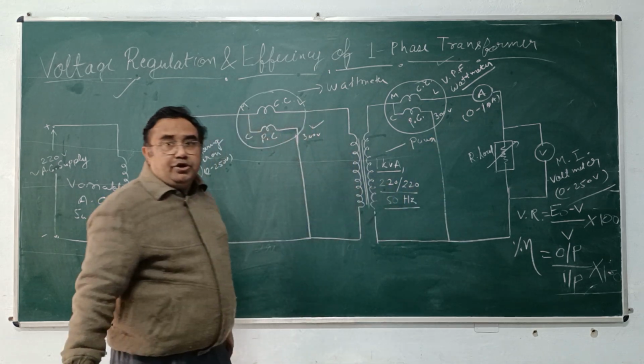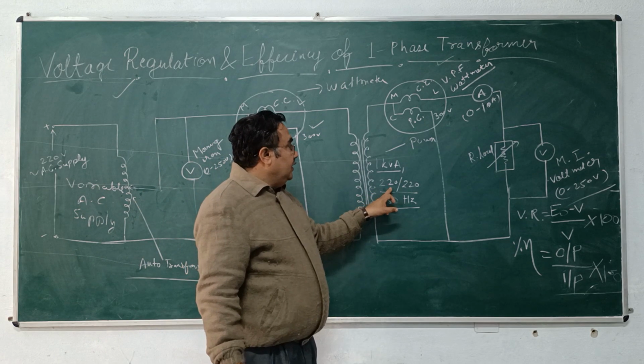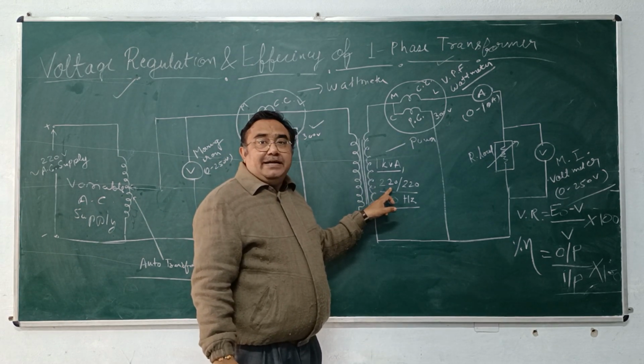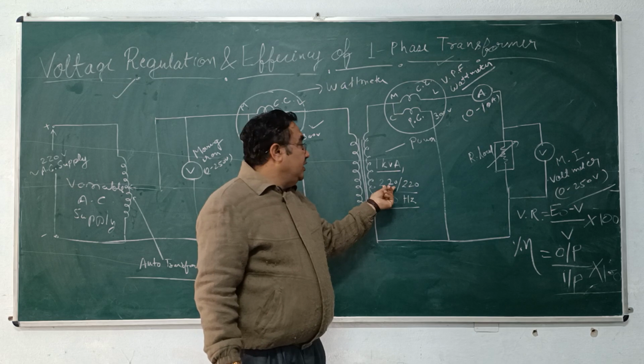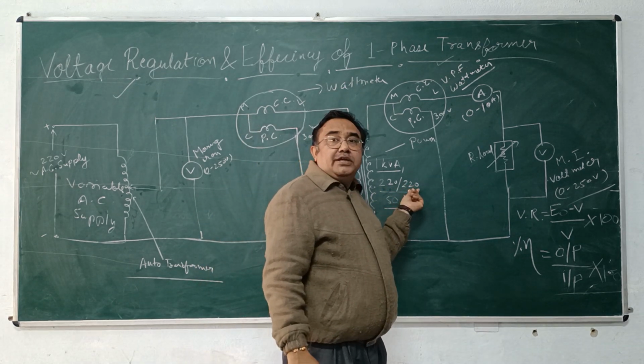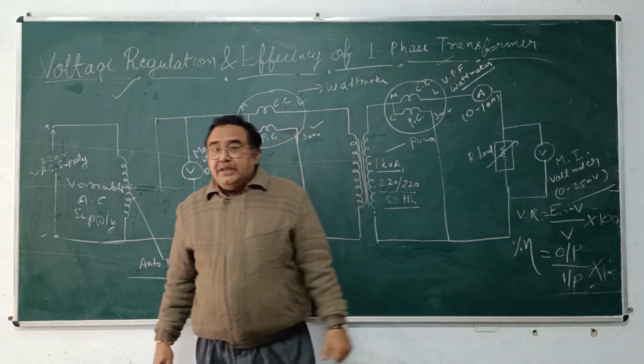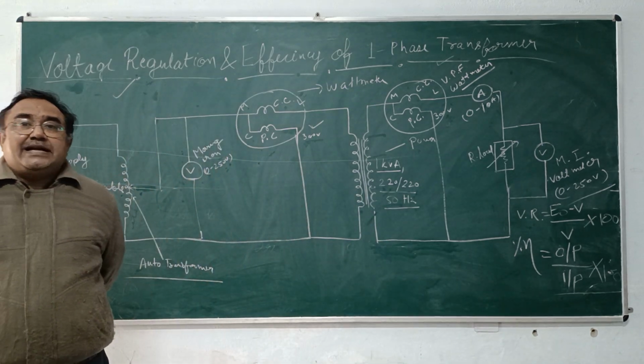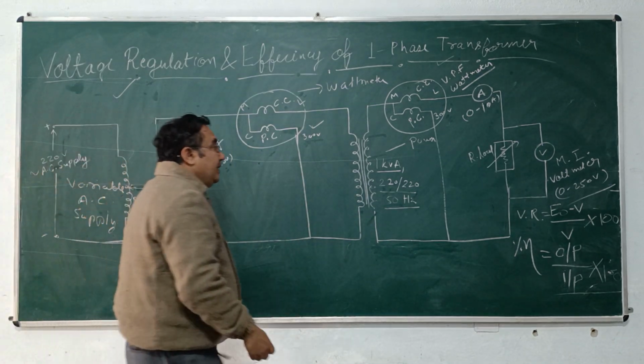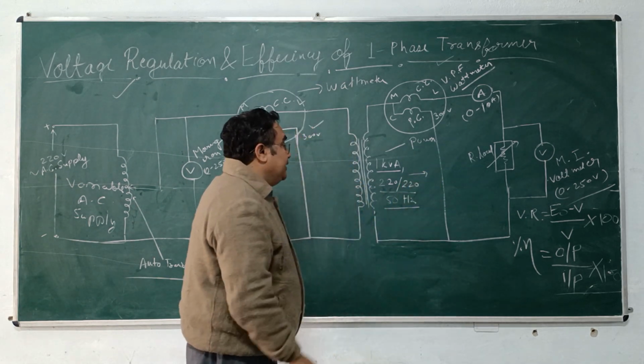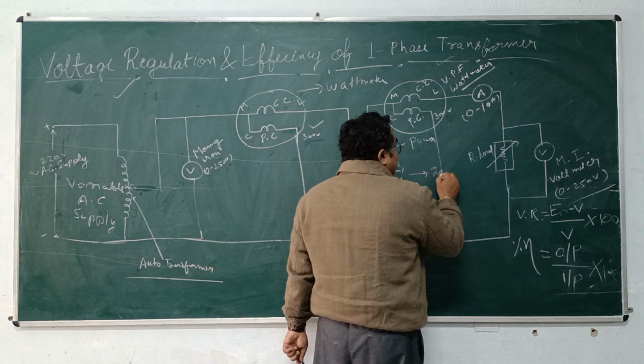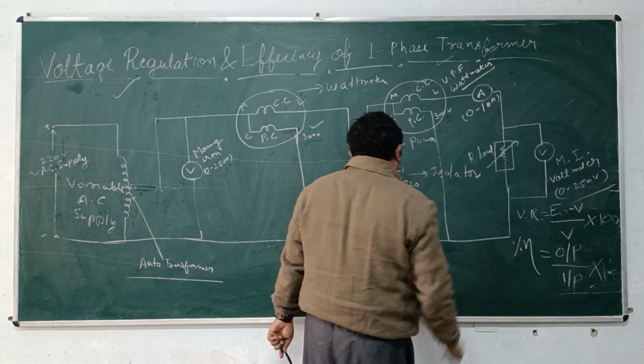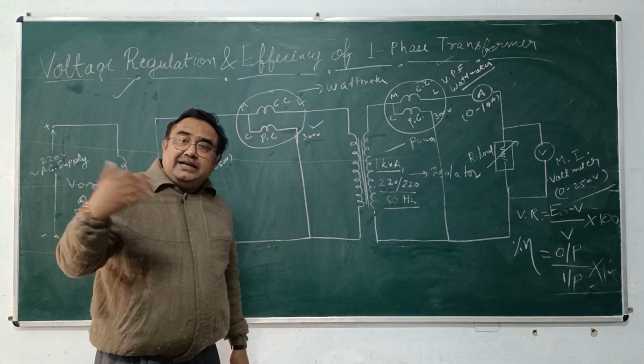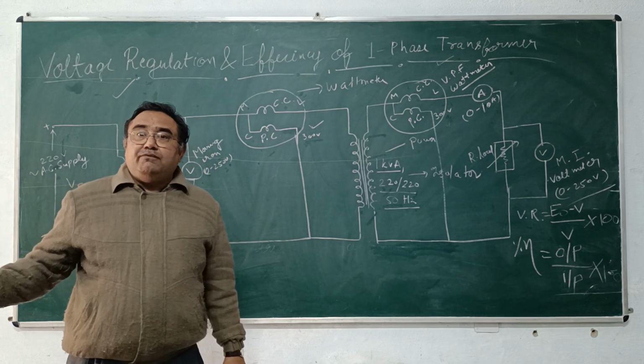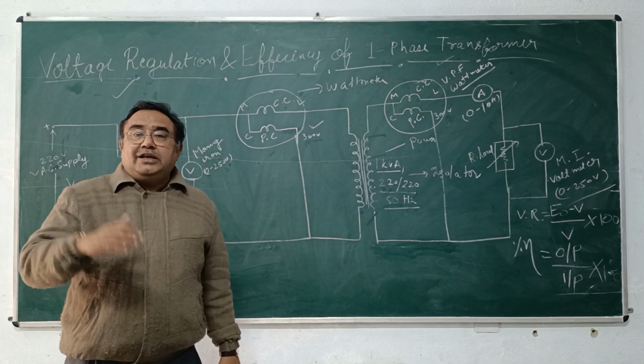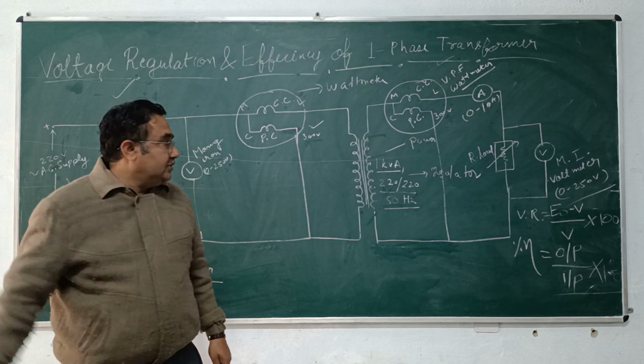As I already told you in theoretical class, the first reading is always of the primary winding, so 220 volt is the primary voltage, and the second reading 220 volt is the secondary voltage. In practice, primary and secondary voltage are different, but here in our laboratory we have the same voltage. This is called an isolated transformer, and it is generally used in college level laboratories. Practically you generally have ratings like 11 by 440 volt, or 440 by 11, or 330 kilovolt by 11 kilovolt.